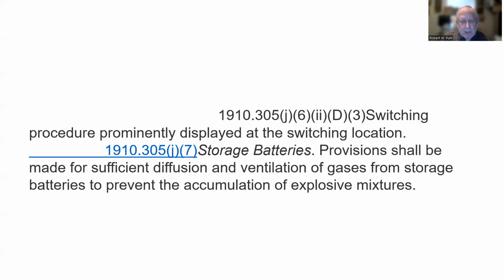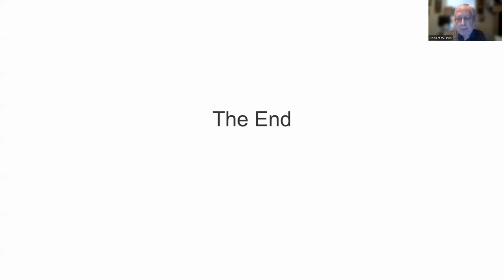Storage batteries. Provisions shall be made for sufficient diffusion and ventilation of gases from storage batteries to prevent the accumulation of explosive mixtures. They just mean batteries, and batteries are basically storing electricity, right? But if you have a battery operated forklift, you have a charging room, and that's one of the things I would think would apply here. They do produce gases, and you need to get them out of there. And that's it for that section.